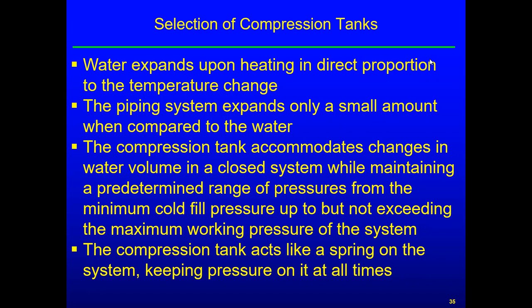I went back a couple of slides just to review from where we've been. We know that water expands upon heating, in direct proportion to temperature change. And so we have to accommodate that expansion in volume. The piping system will expand a little bit when you heat it up, but not nearly as much as the water. So we've got to have some volume out there, and that's the compression tank that the water can expand into. Pressure will rise as it expands, increasing the pressure in that compression tank. If it's designed properly, it will go up to a design maximum, which will not blow the relief valve.